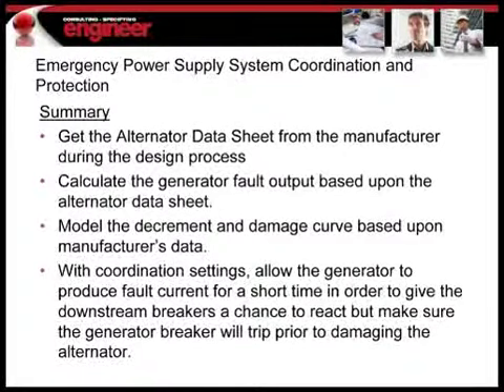It's also useful to take that fault output and make sure that your fault calculations match that output, that hand math. Then you're going to have to model the decrement and the damage, compare that to the manufacturer's data, and then start setting your breakers. And like I said, once you start off the top at the generator, you set that breaker, then you start setting the breakers downstream. And then that's pretty much it.